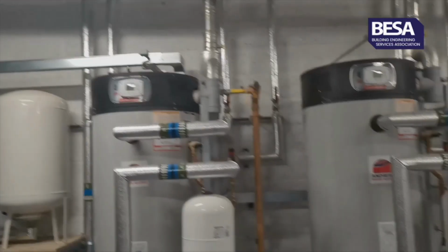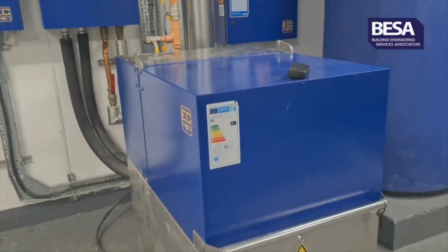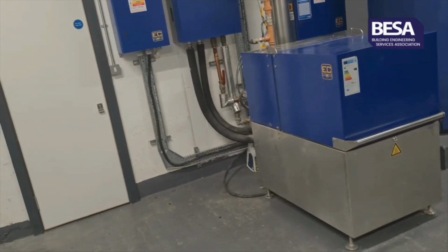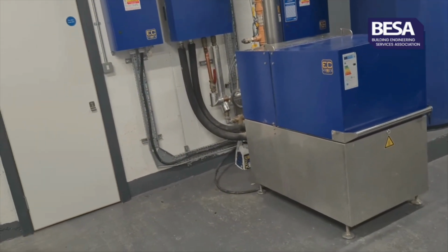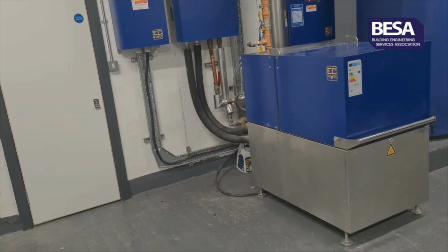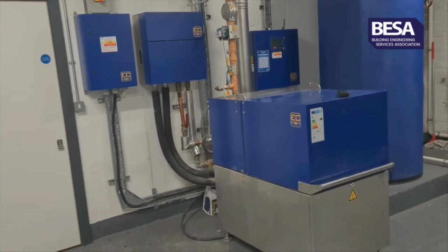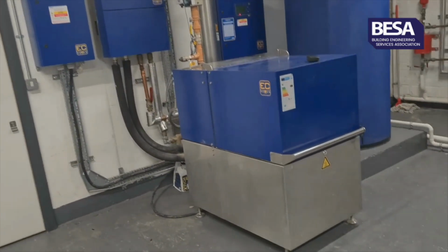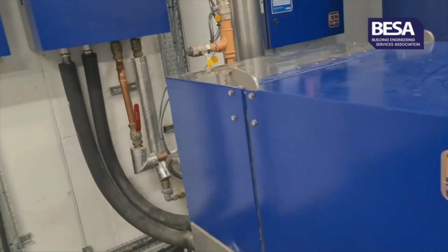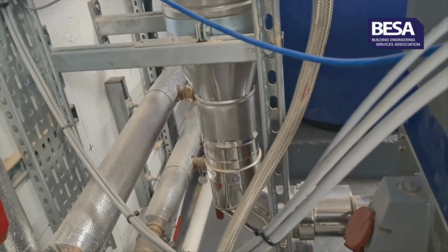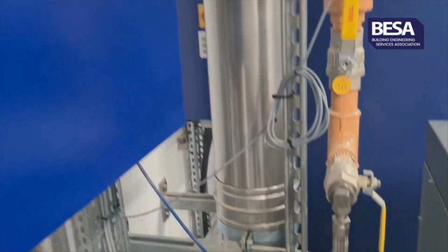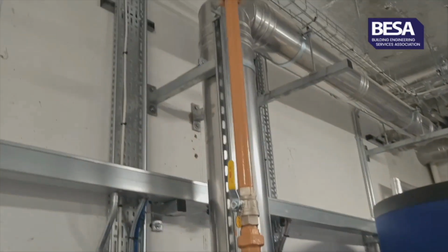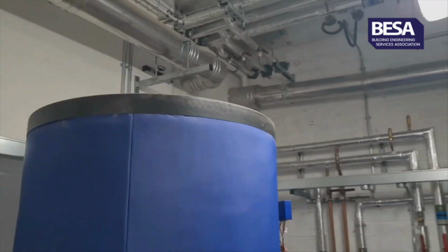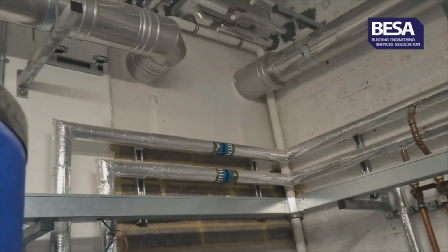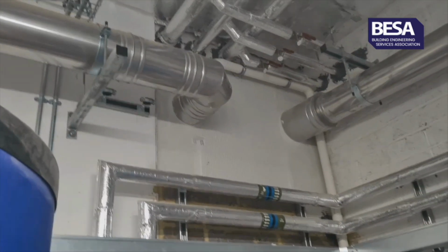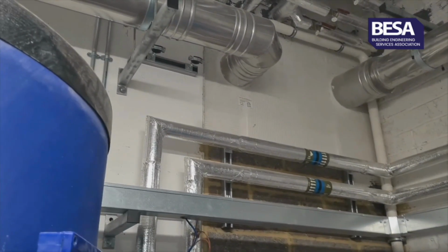So that's the gas-fired water heaters. If we come over to the CHP machine, there it is. So the CHP, again, non-domestic Gas Safe certification, and has been sized in compliance with CIBSE AM12. There's a flue off the back of the CHP. It was installed by the same supplier as the gas-fired water heaters. As you can see, it comes up to twin wall flue. It again takes the same route through there into a riser, which goes right to the top of the building, three stories up.